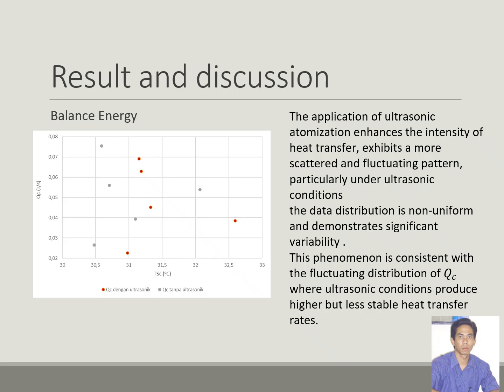Based on the energy balance analysis, it can be observed that the ultrasonic condition results in a relatively higher error compared to the conventional system without ultrasonic actuation. This finding indicates that although the application of ultrasonic atomization enhances the intensity of heat transfer, not all of the supplied energy is effectively transferred to the cold fluid side. Instead, a portion of the energy is stored as internal energy within the system, or associated with non-ideal effects such as acoustic energy dissipation and microscale fluid motion. This phenomenon is consistent with the fluctuating distribution of QC observed in the graph, where ultrasonic conditions produce higher but less stable heat transfer rates.